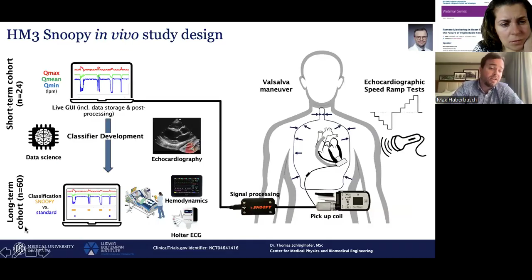So the parameters they could monitor this way included the average HeartMate 3 pump speed, then the mean, minimum, and maximum of the pump flows and the HeartMate 3 motor current. Of course, the pulsatility index, the overall current uptake, and the HeartMate 3 rotor's radial center displacement and the variations around it. And they could record with an error-free data rate of more than 90%, as confirmed by CRC checksums.